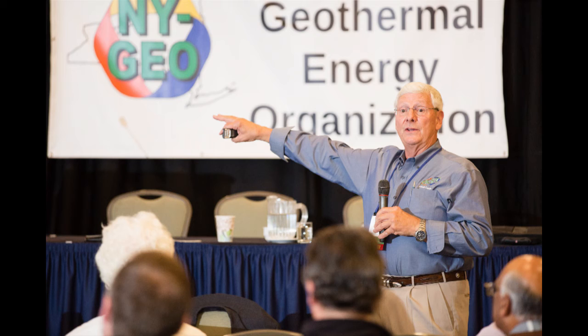Anyway, we're looking at just initially, this slide was actually made the middle of last year. We were looking to have a couple of new boreholes because we had some extra square footage that we could use underneath a basketball court. We were looking at a central loop expansion of an additional 2,200 linear feet of 18-inch pipe. Maximum summer temperature for the loop right now is 86. Minimum winter is 50. We're up to 62.